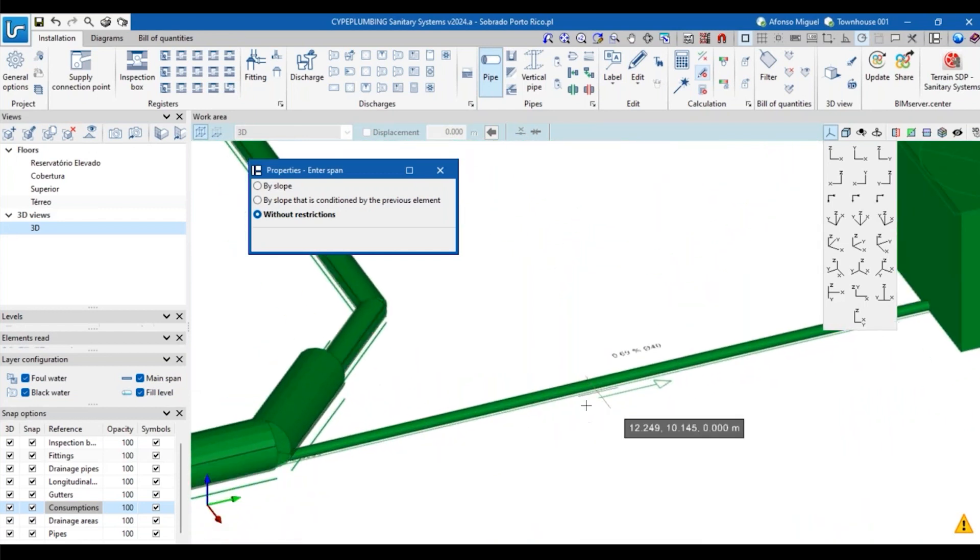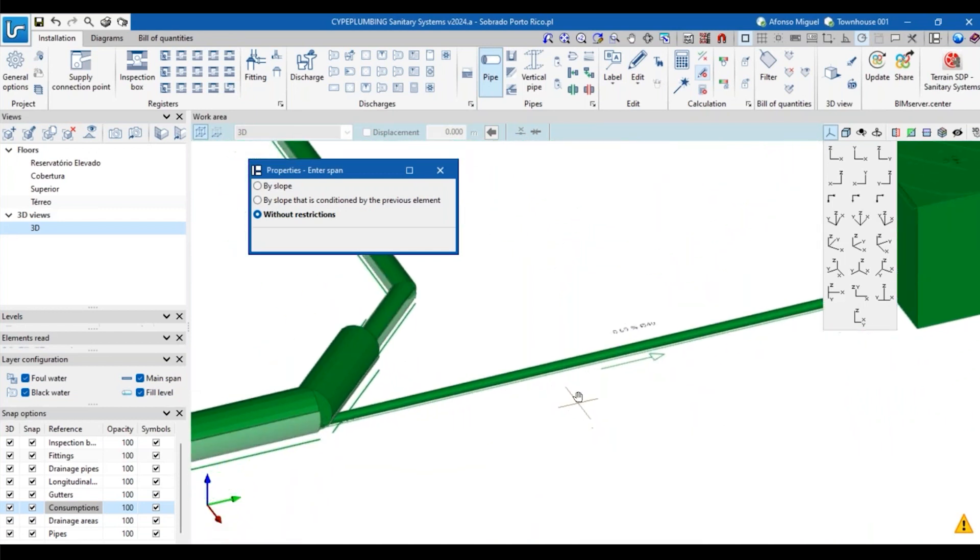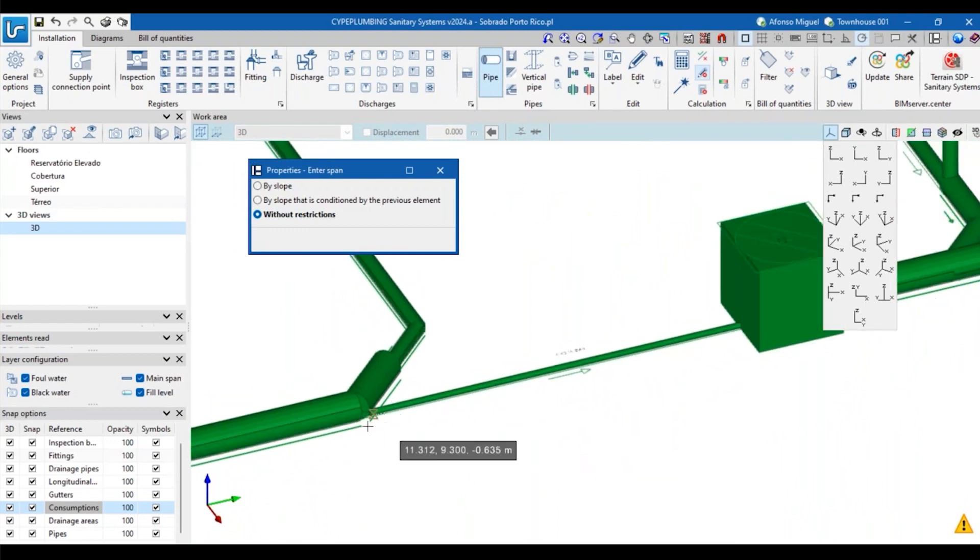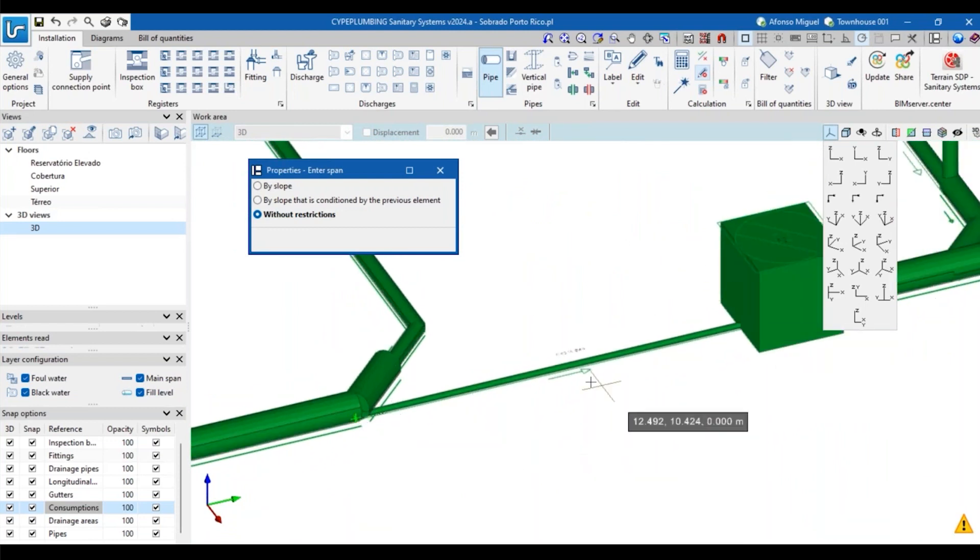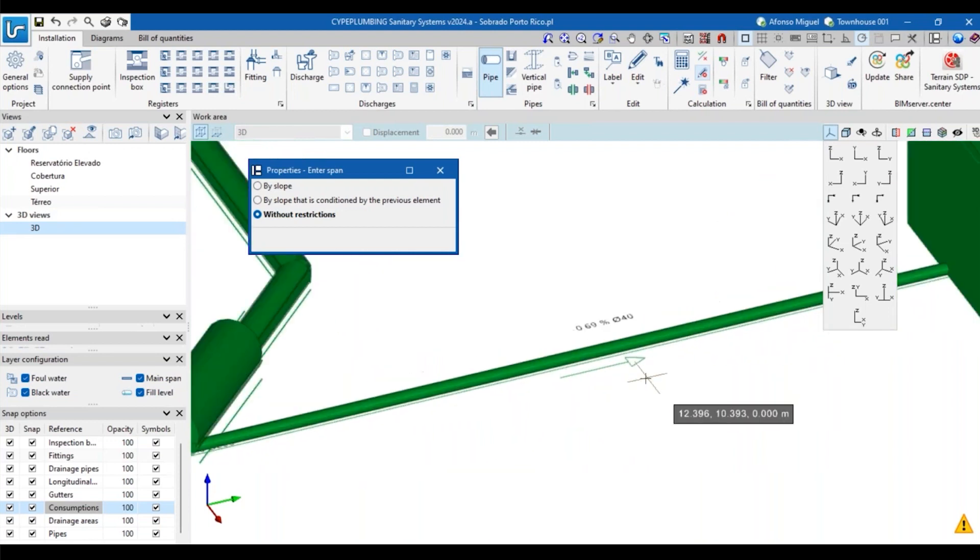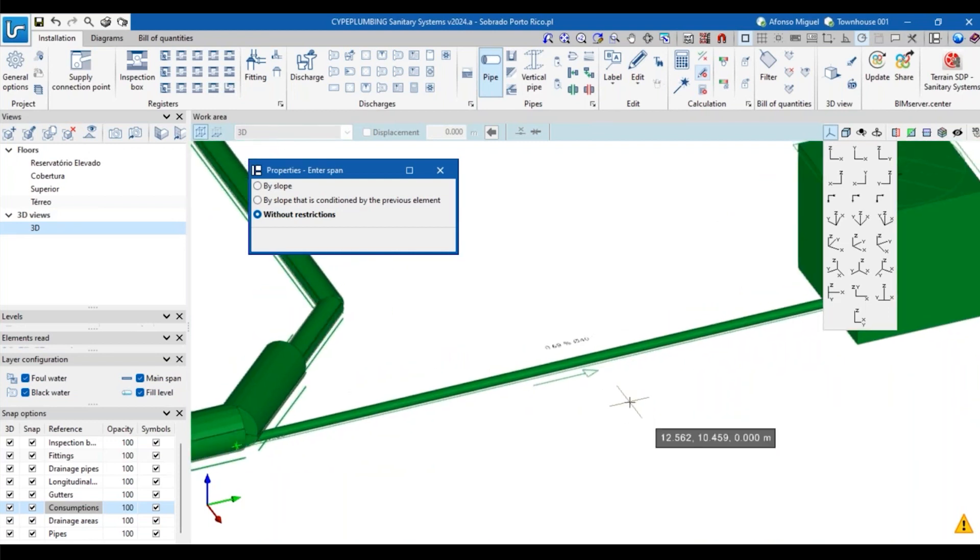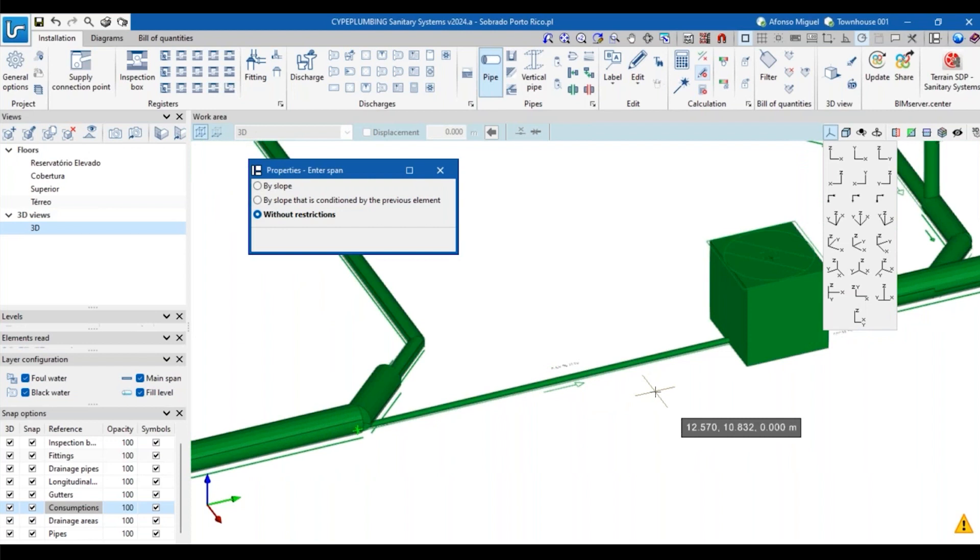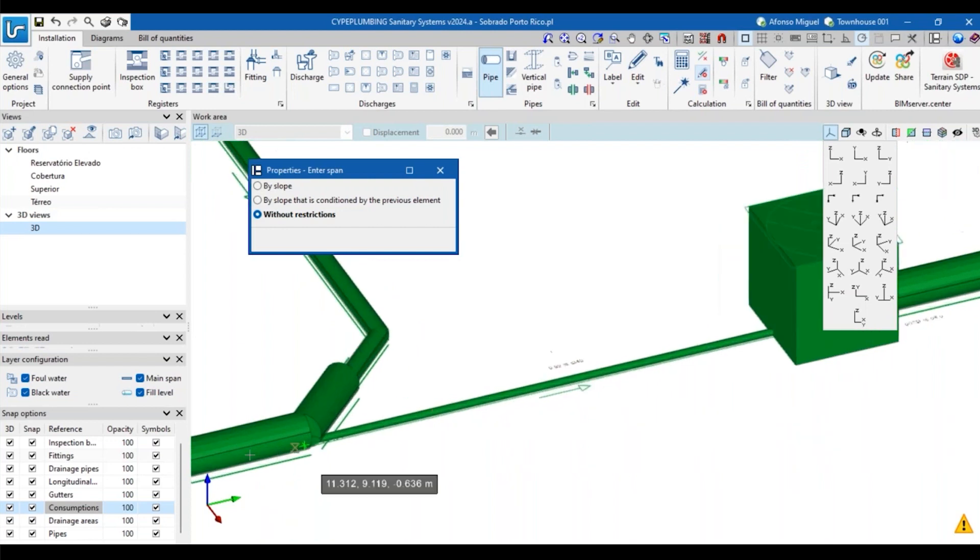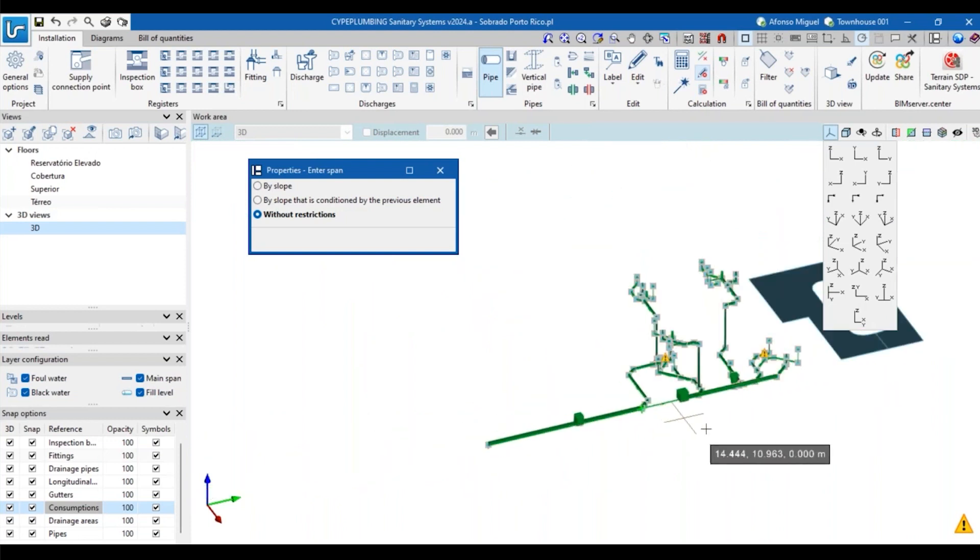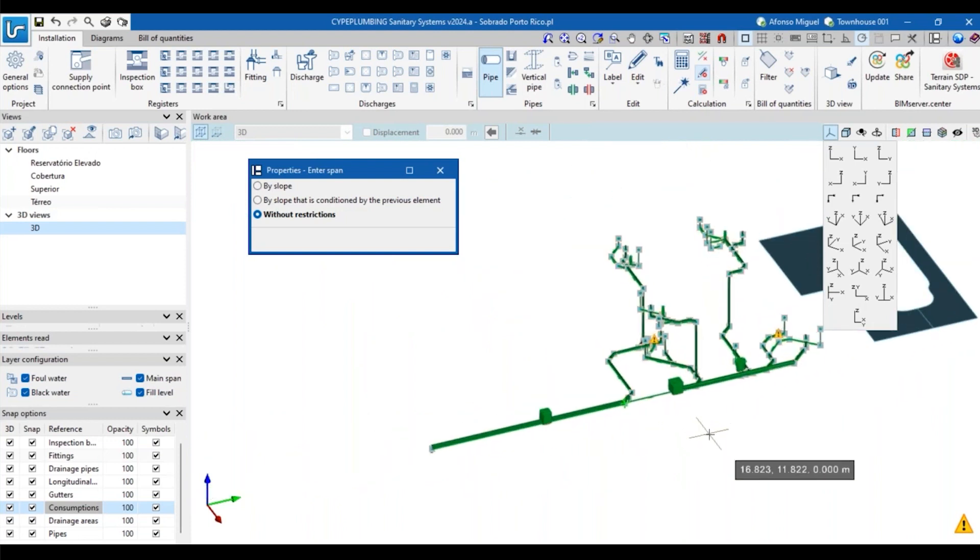Two details that we must know here that are very important: the first thing is, as I started introducing the first point here and the second point here, this arrow indicates the direction of the flow. In this case we are talking about pipes that work by gravity, so it's very important to know the direction. If we are working with slopes, we must be sure that the slope is in the direction of the flow. So I've been introducing from here to here, but as you can see, if I zoom out in my installation, probably the water is coming from the upper level and coming in this direction until this end point.